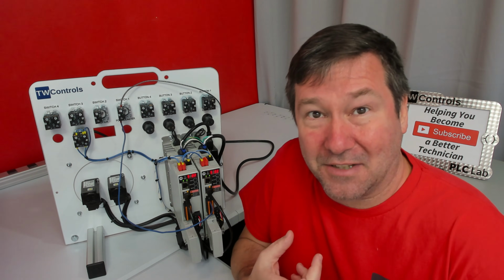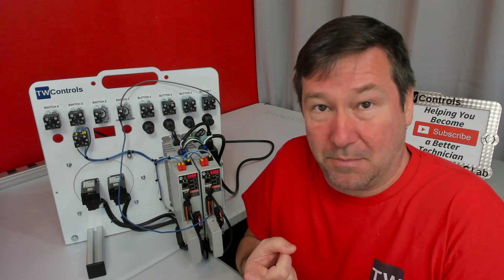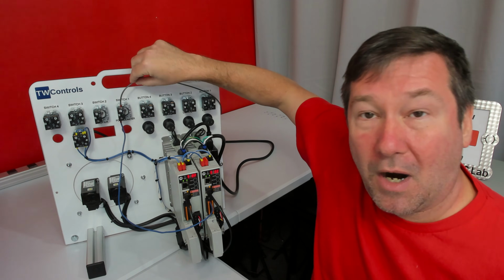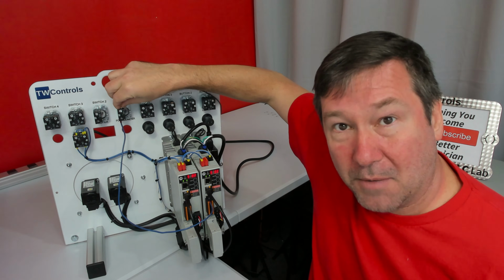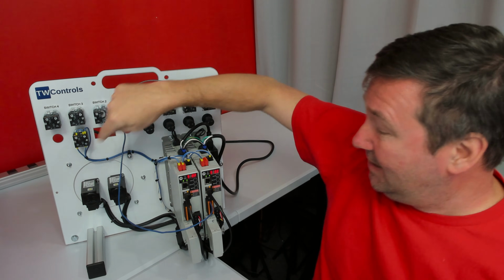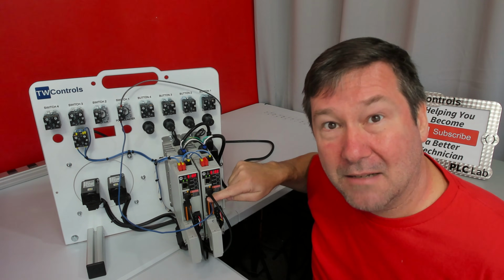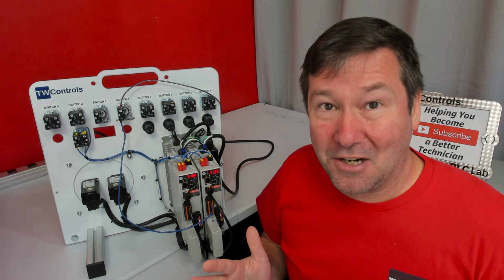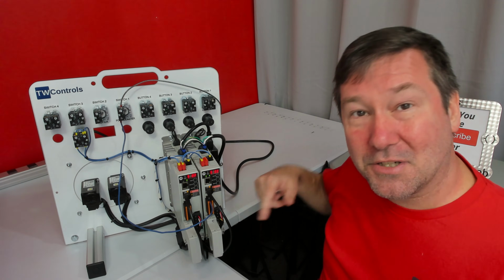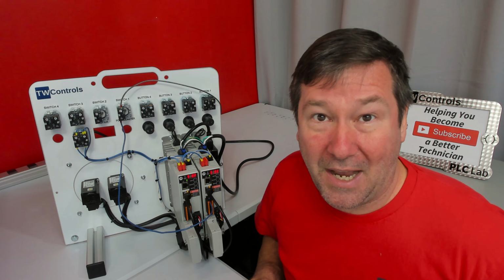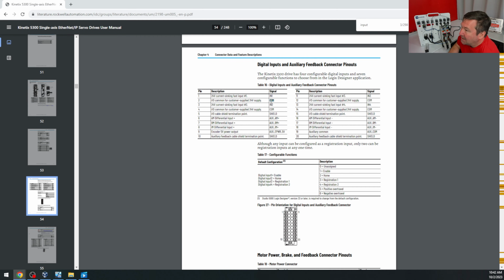And the reason why you ask yourself that is that tells us, okay, is our power supply good? Did I bring a wire to one side of my switch from the positive of that power supply? Do I have a wire going to that input? And then most often overlooked is, do I have a return back to the minus of the power supply? And that common is right here on pin number 2. It says IO common for customer supplied 24 volt.